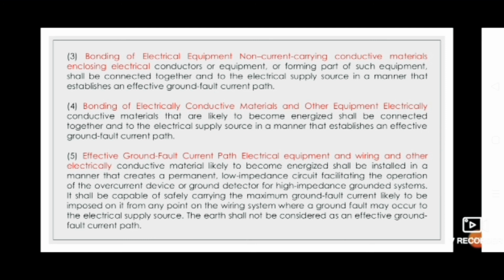And the last, the effective ground-fault current path. Electrical equipment and wiring and other electrically conductive material likely to become energized should be installed in a manner that creates a permanent, low-impedance circuit to facilitate the operation of the overcurrent device or ground detector for high-impedance grounded systems. It shall be capable of safely carrying the maximum ground-fault current likely to be imposed on it from any point of the wiring system where a ground fault may occur to the electrical supply source. The earth should not be considered as an effective ground-fault current path.